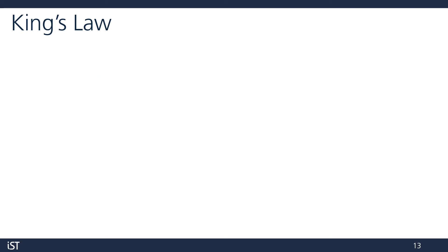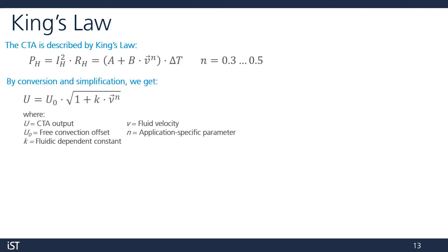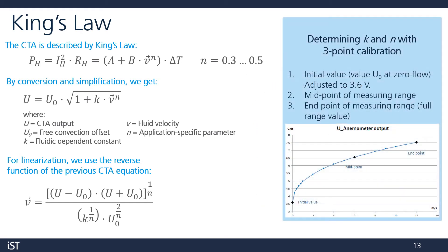How do we characterize our CTA results? The CTA is described by King's Law. We convert and simplify it to get a formula where U represents the CTA output in volts, then use the reverse function and linearize. The K and N values can be determined by performing a calibration using three points: zero flow, the midpoint of our flow measurement range, and the upper limit of this range. For a more detailed description and an example calculation, take a look at our application note.